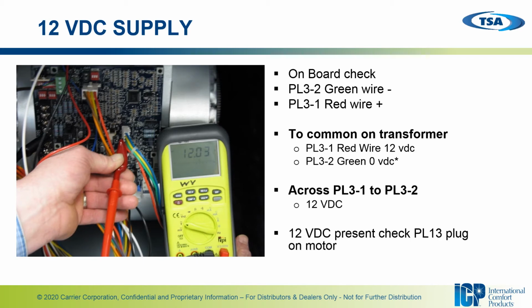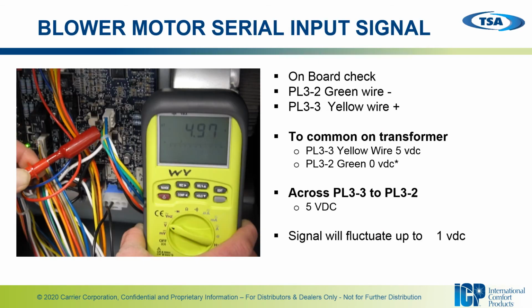So when troubleshooting from the board, you're going to want to check between the red wire and the green wire. Okay. Between the red wire and the green wire, you should read 12 volts DC. If that voltage is present, then check plug 13 on the motor. Now, that was your 12 volt DC supply power to the motor.